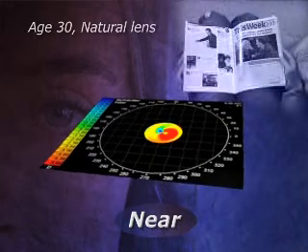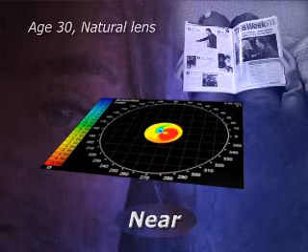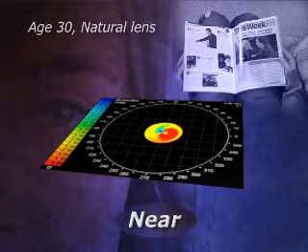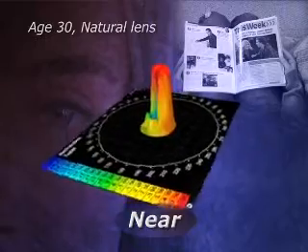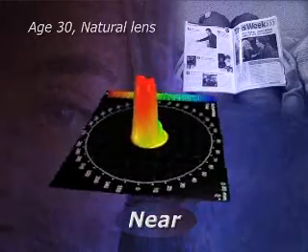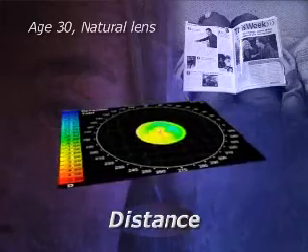This wavefront shows the same eye focusing on a near object, such as a magazine. This wavefront has a red hot spot in it, which indicates a dramatic increase in the near focusing power of the eye. As the red spot increases in power, the blue area surrounding the red spot decreases in power. This is a normal accommodative response in a younger person.